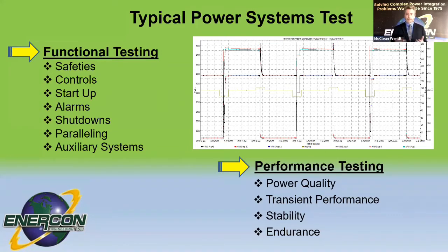At that point, then we'll make sure that the voltage is coming up to the right level, that the phasing is correct on both the sensing PTs and the load. We'll make sure that the CTs also have the correct polarity and are reporting to the controller the proper values. The next step would be to test alarms and shutdowns.